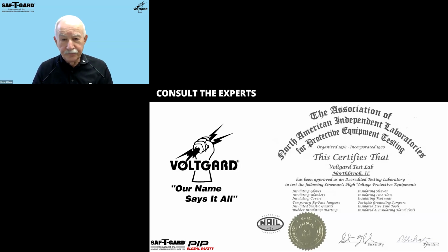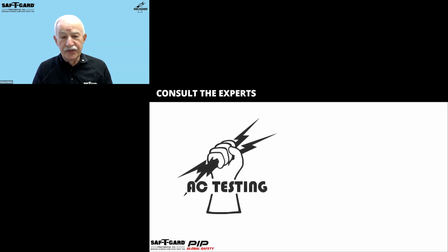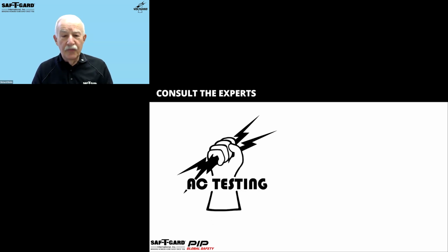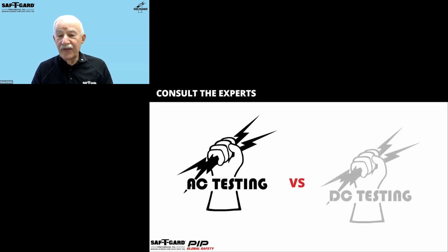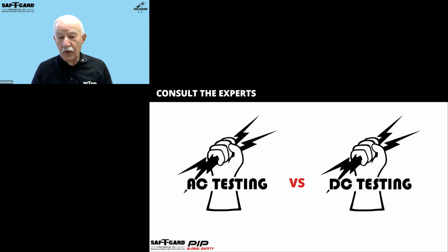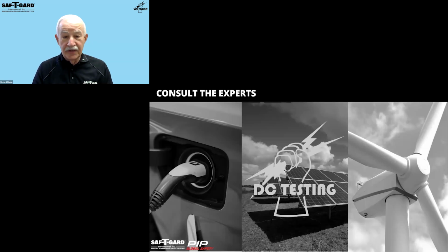Now, electrical testing is not just reserved for AC voltages. I referred to DC testing earlier, and DC testing is also available from Voltgard and other test labs. For maximum safety, it is important to understand the application for use and test the rubber insulating gloves as close as possible to that environment. If you're going to be using them in AC, then test them AC. If you're going to be using them in DC, then test them DC.